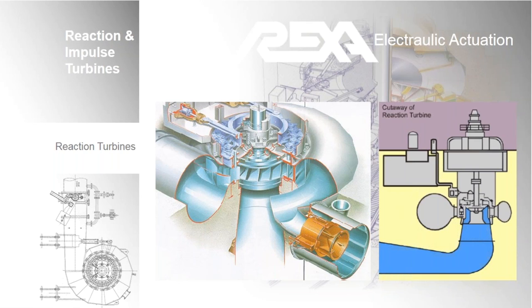Turbine orientation may be vertical or horizontal. To control water flow to the runners, an actuator or servos are used to position wicket gates to a desired set point. Single or double actuated gate rings can position the wicket gates to regulate flow. For a double actuated gate ring, the setup is usually with two actuators operating in tandem that stroke in opposite directions to adjust the gate ring to position wicket gates.